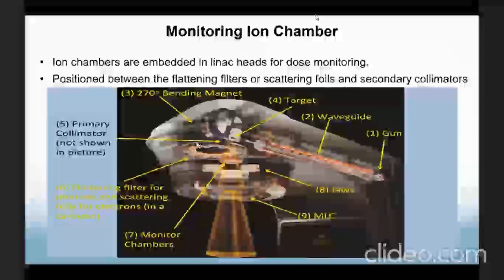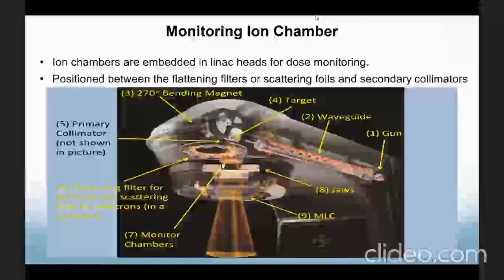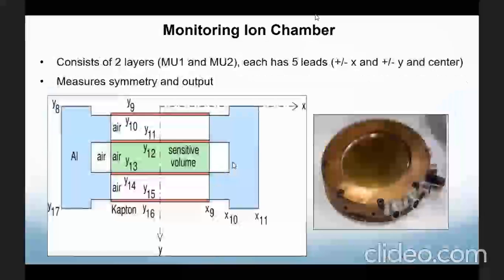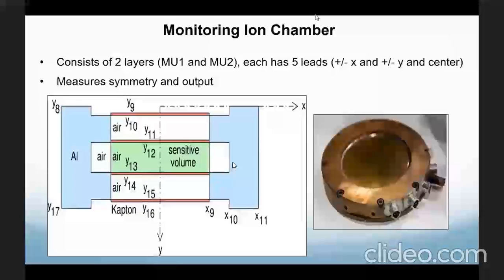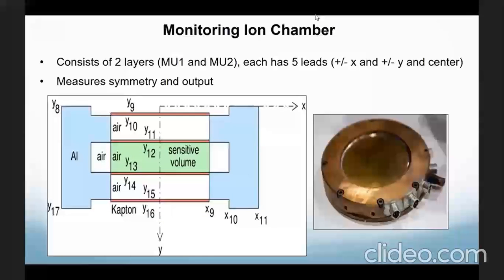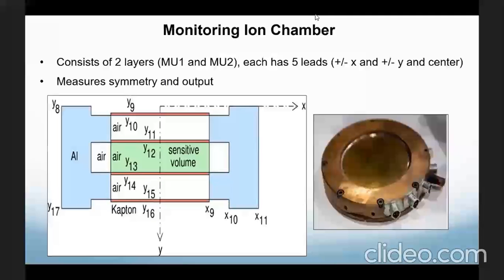The monitor chamber is responsible for quantifying the amount of radiation we are giving to the patient. This is another view, another picture of the chamber. It has a sensitive volume, and it has two layers in the machine — in the Varian — which has two MUs: MU1 and MU2. It has five leads: plus/minus X, plus/minus Y, and another lead in the center to measure. This chamber measures output as well as the symmetry of the beam.